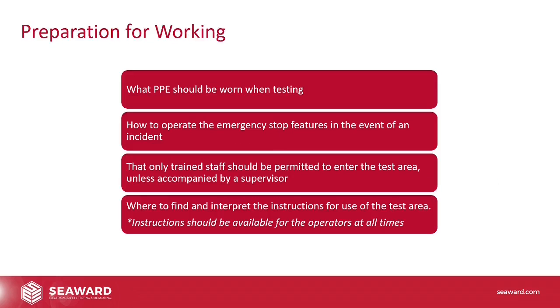So in terms of preparation for working, we need to consider what PPE should be worn. So is it insulated boots? Is it insulated gloves? We need to think about how we operate the emergency stop features in the event of an incident. So the operator needs to know that switch is there and how to use it, and other people around should know how to use the emergency stop outside the area if the operator is in trouble. We need everyone to know that only trained staff should be permitted to enter the test area unless accompanied by a supervisor. And where to find and interpret the instructions for use of the test area.